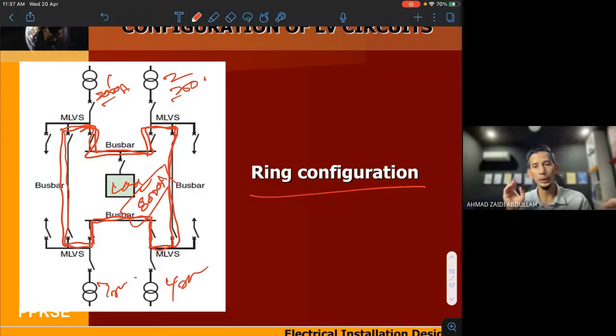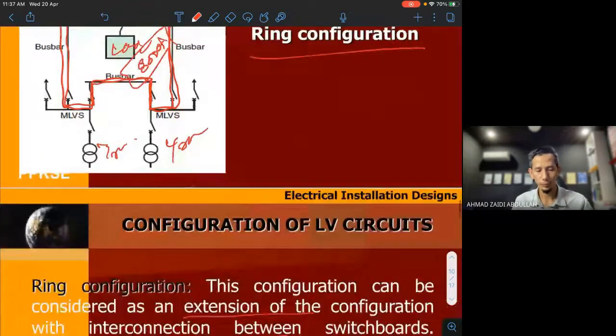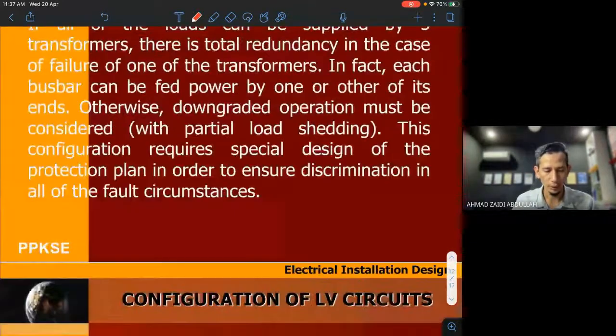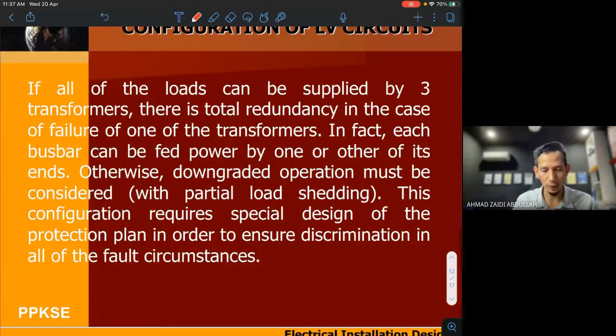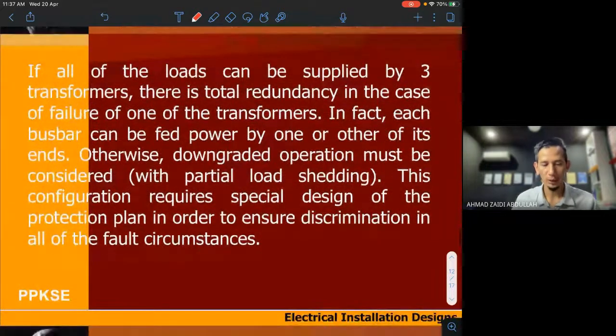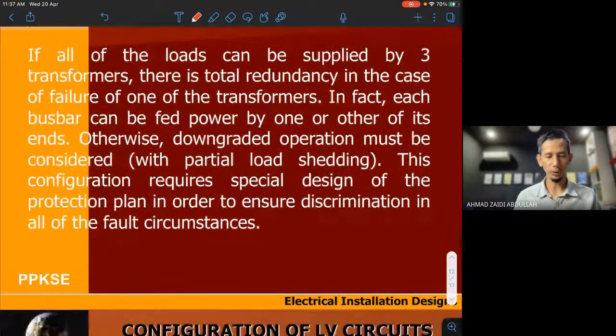So normally we make it a parallel transformer with the separation looking like this, the configuration. So we try to spread. Instead of you buying an 8000 amp transformer, compared to the 2000 by 4, you still can get a lot of saving. Okay, and then if all of this load can be supplied by 3 transformers, there's total redundancy. In fact, each busbar can be fed.